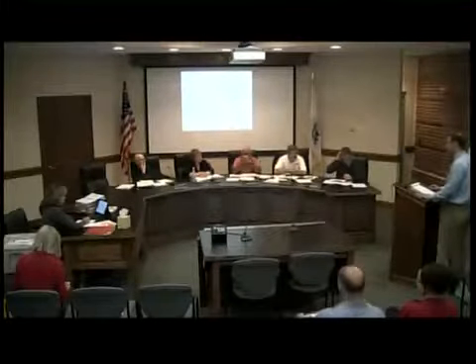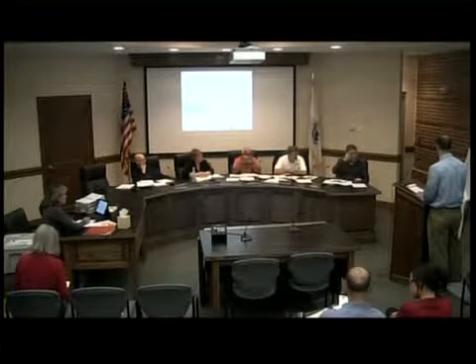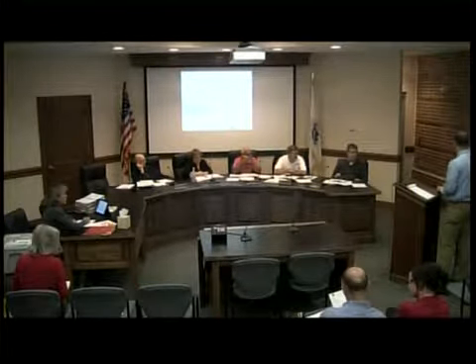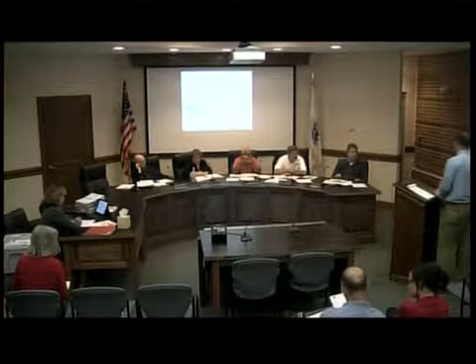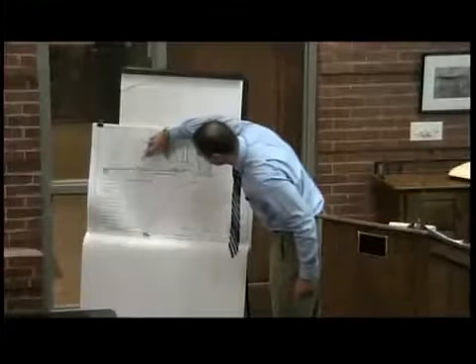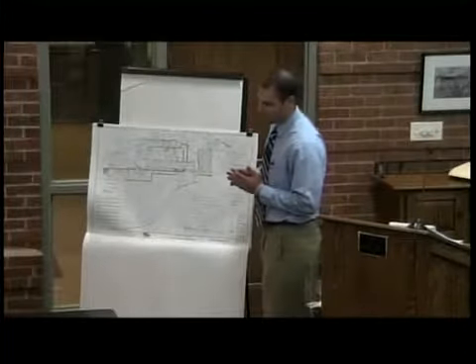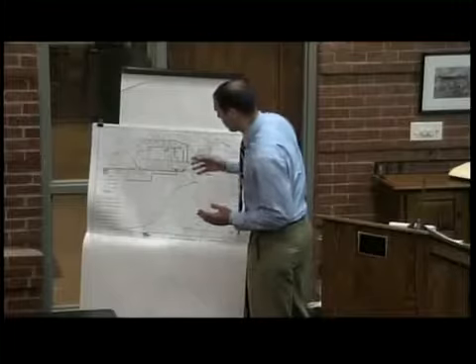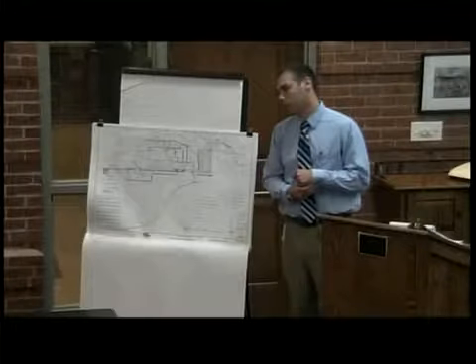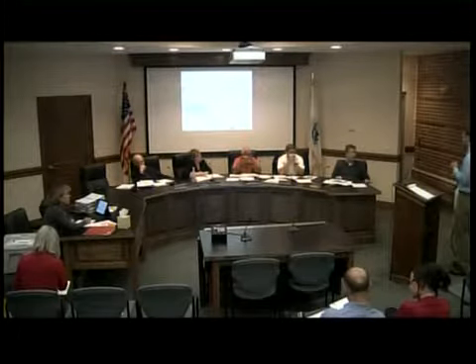So, any questions? I can take questions. Yeah, sure. You mentioned transformers on the new switchgear pad. Transformers will be replacing where they're located on the existing pad. You'll have new transformers? New transformers, yeah. Currently, the existing transformers are shown here and here. The new transformers are going to be just off to the side. And we can install one at a time, because we don't need both transformers at once. However, we need to construct the switchgear before the existing switchgear gets demolished. Okay, good. So the transformers aren't in the same location as the new switchgear? Correct.